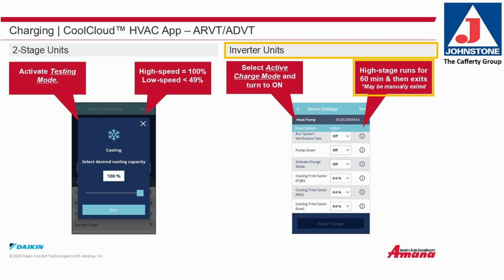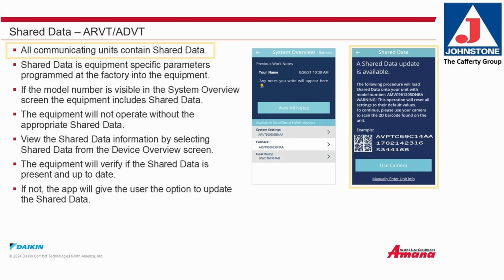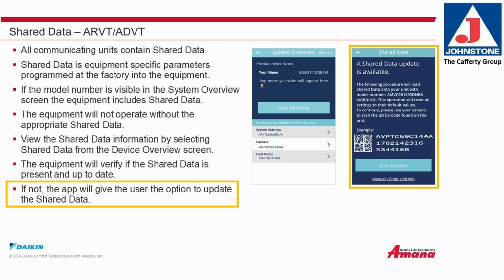Shared data. All communicating units contain shared data. Shared data is equipment-specific parameters programmed at the factory into the equipment. If the model number is visible in the System Overview screen, the equipment includes shared data. The equipment will not operate without the appropriate shared data. View the shared data information by selecting Shared Data from the Device Overview screen. The equipment will verify if the shared data is present and up to date. If not, the app will give the user the option to update the shared data.